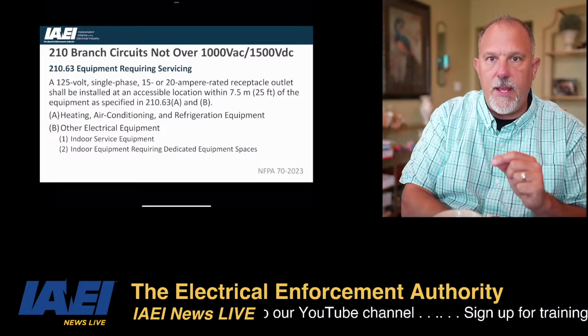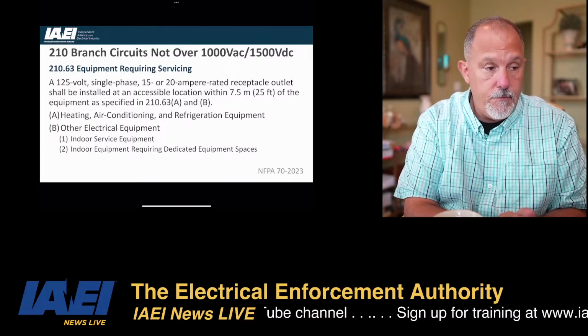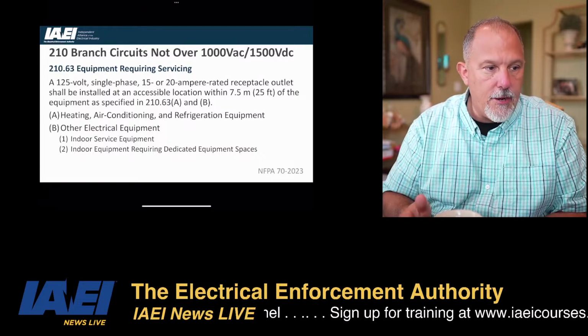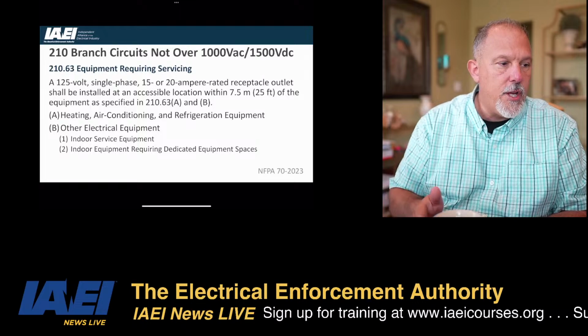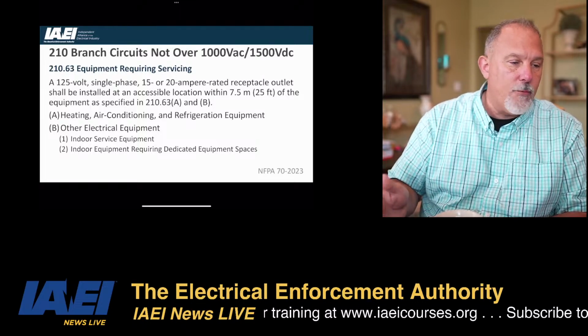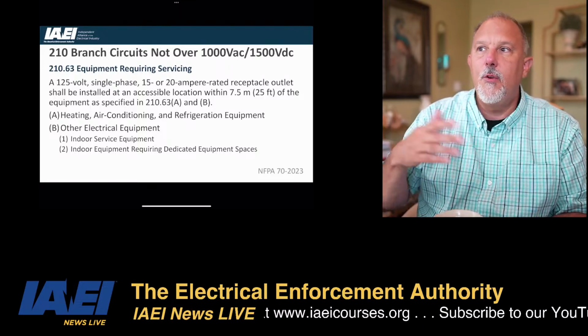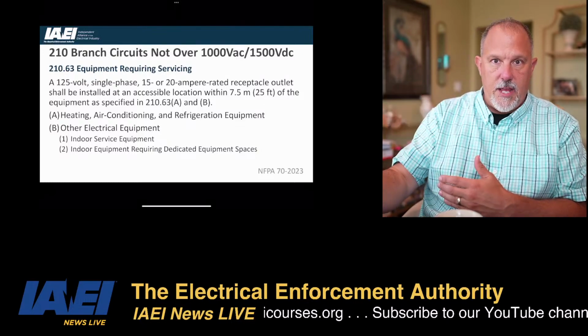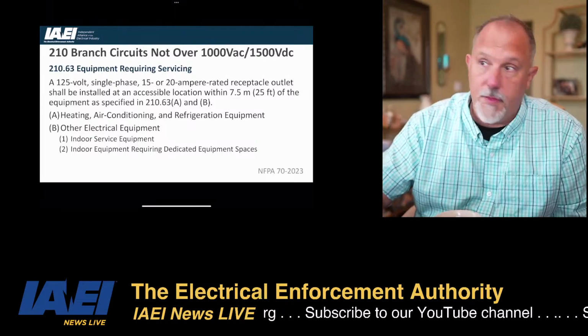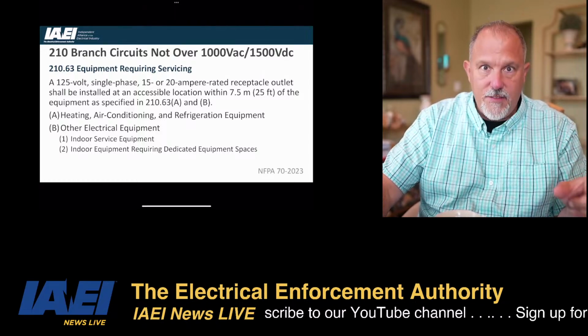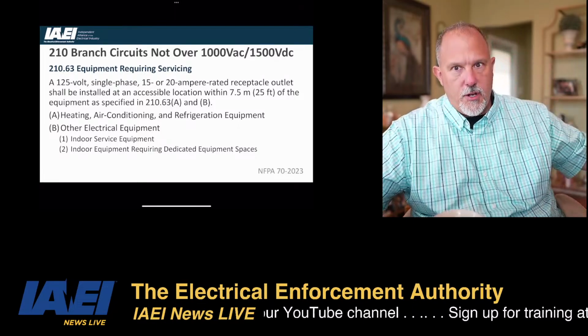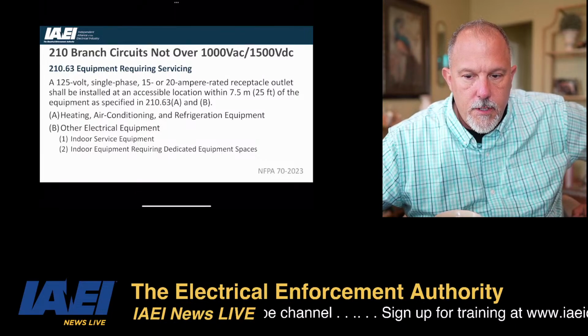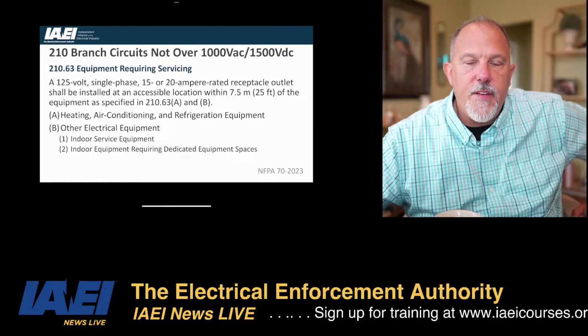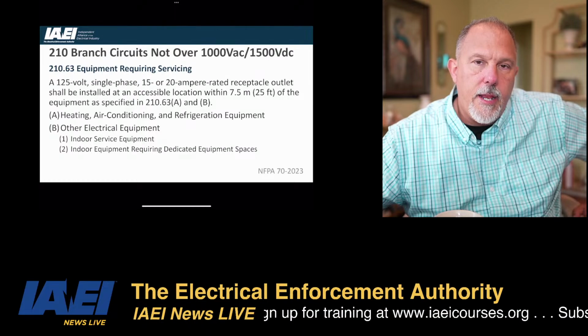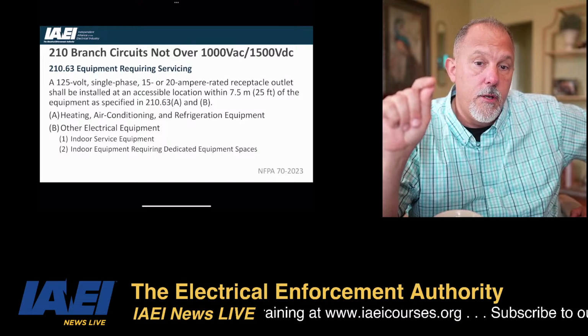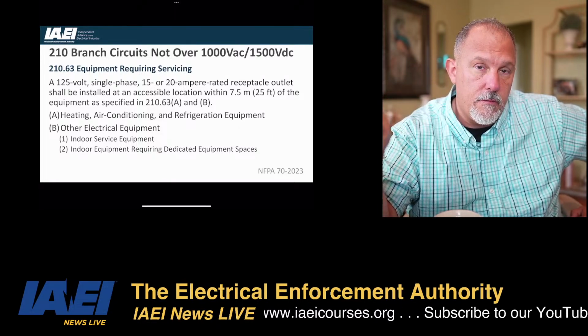And in 210.8, we have a requirement that receptacles be GFCI protected. So in 210.63, we say heating, air conditioning, and refrigeration equipment is going to need a receptacle, and indoor service equipment and indoor equipment requiring dedicated equipment spaces requires a receptacle to be placed there. And then again in 210.8, we're saying, hey, you better GFCI protect the daggone thing. So that is, I think, an effective use of the term servicing, and an appropriate code requirement that is related to the topic of servicing. Make sense?